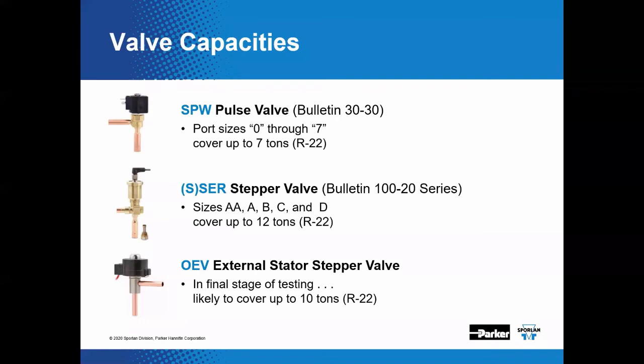Yes, sir. Net refrigerating effect comes in kind of indirectly because something that we need to know when sizing any of our valves is what refrigerant's in the system. And we need to know the conditions on the high and the low side of the system. So that inherently is going to bring the concept of net refrigerating effect into play. Now, as far as the capacity that's utilized, we match the thermostatic expansion valve to the capacity or the load on the evaporator. That makes the most sense, because what does a thermostatic expansion valve do? Its sole job is to control superheat in the evaporator as a result of monitoring at the sensing bulb, wherever that's placed. So it's important to know what kind of load is going to be imposed upon the evaporator coil. Okay. All right. Thank you, Jim.